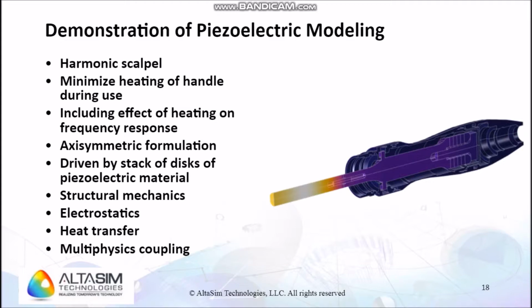There are several issues that we sought to address in this design. One was to minimize the heating of the hand unit so that the surgeon could hold it comfortably. Another was to include the effect of heating on the vibrational response of the device, including the shape change and the additional stress on the piezoelectric materials.